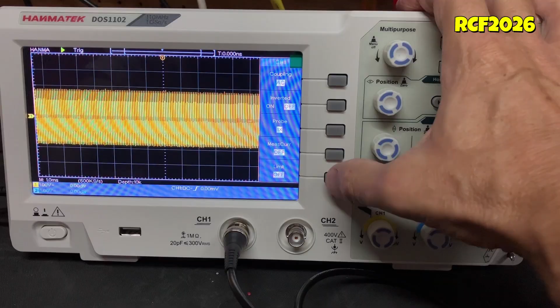Set up channel 1 to accept the input signal, making sure the correct coupling type is selected for the signal being measured. Also check the probe type setting and select either X1 or X10, depending on the probe being used. The limit button allows you to limit the oscilloscope's input bandwidth. Setting the limit to 20 MHz reduces unwanted higher frequency signals and noise, which can provide a cleaner waveform and improve measurement accuracy when working with lower frequency signals.